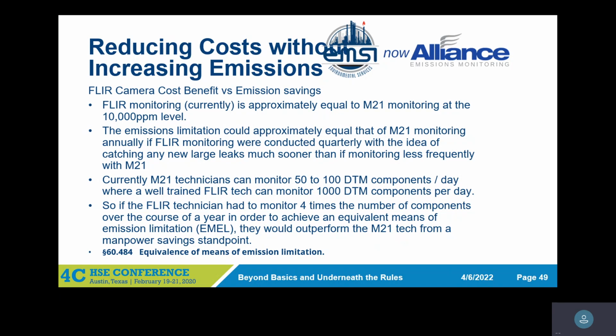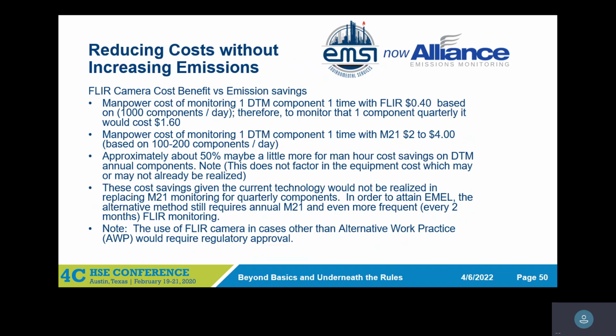So you would do a gas check, right? There's technically a calibration for the FLIR camera. That's something that the actual manufacturer does. There's no routine, like daily or weekly calibration. It's called a gas check. And that's where you would actually do what we were talking about earlier. In the morning, you set up that bottle, you set up the known flow rate of methane going out, and see what distance you can see it at, right?